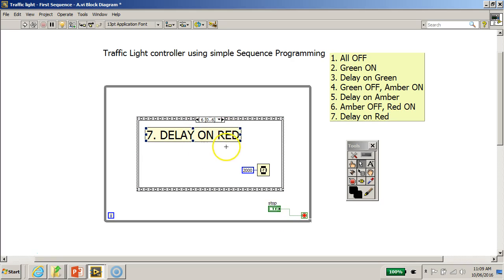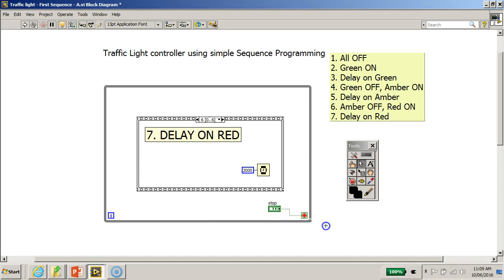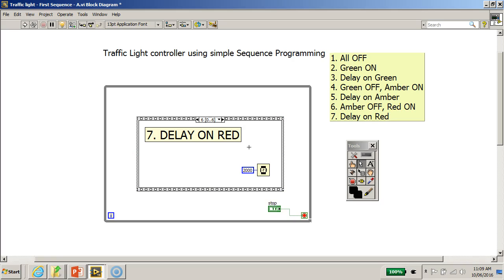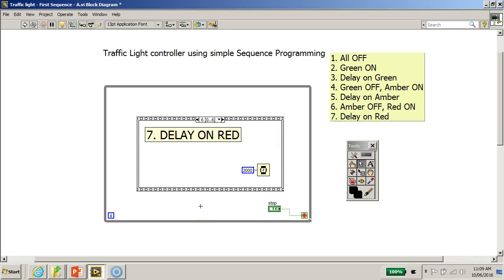Then only the program has terminated. So this is one of the key disadvantages of using sequence programming. The program will not be able to be terminated instantaneously or immediately whenever the operator hits the stop button. So this is one serious drawback for using sequence programming.